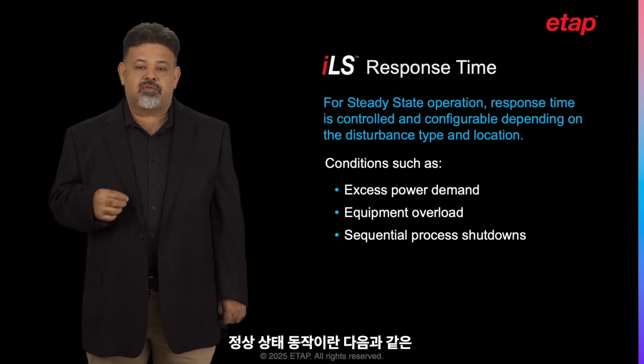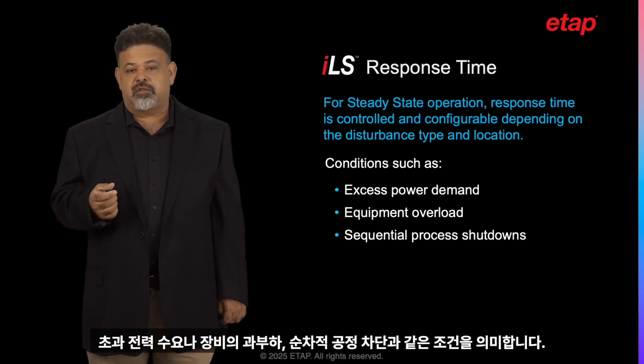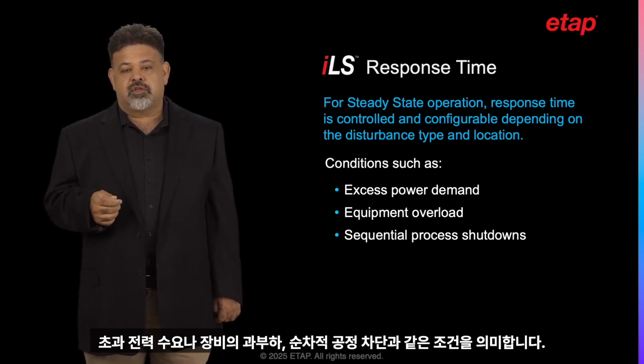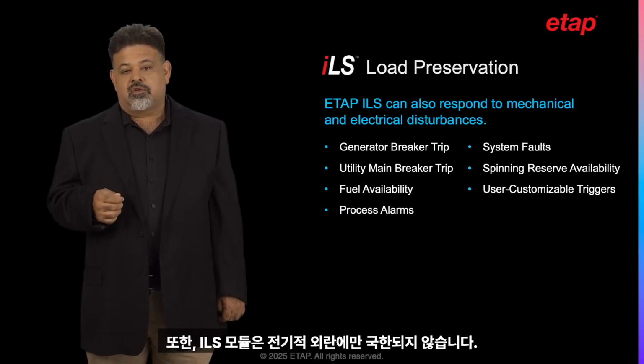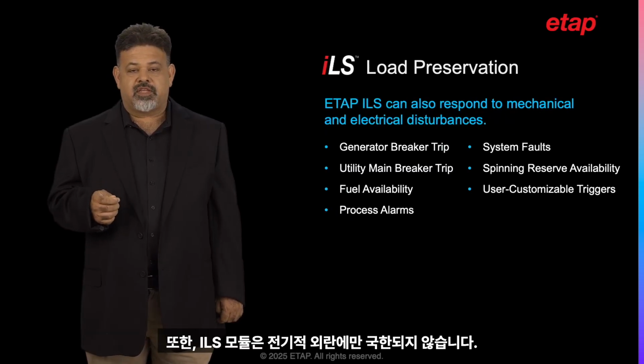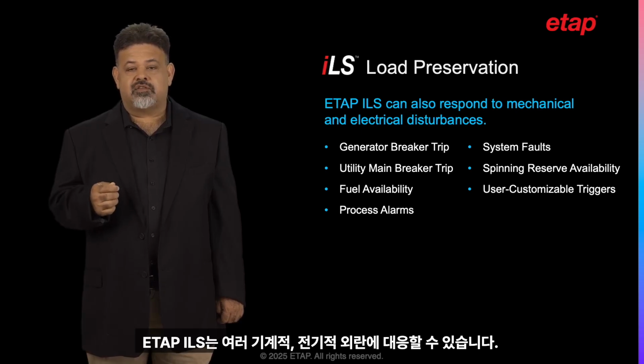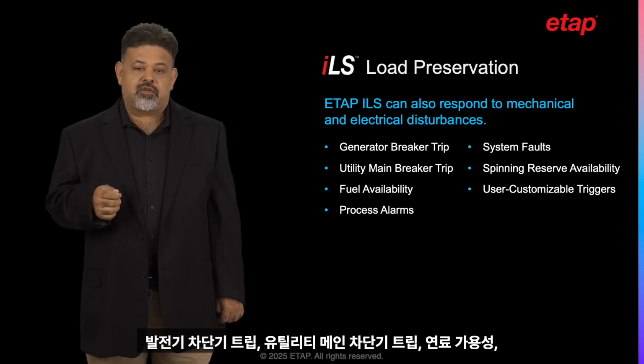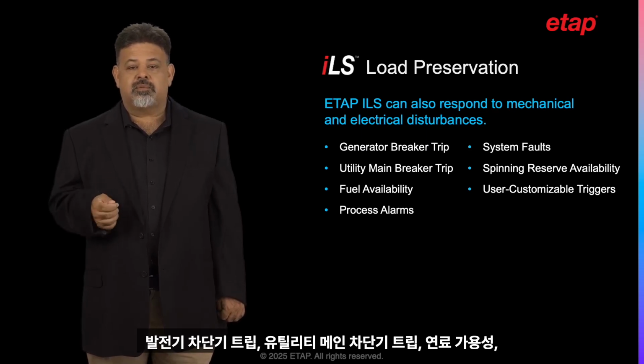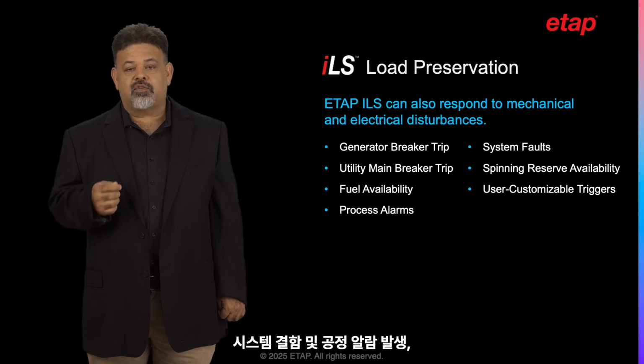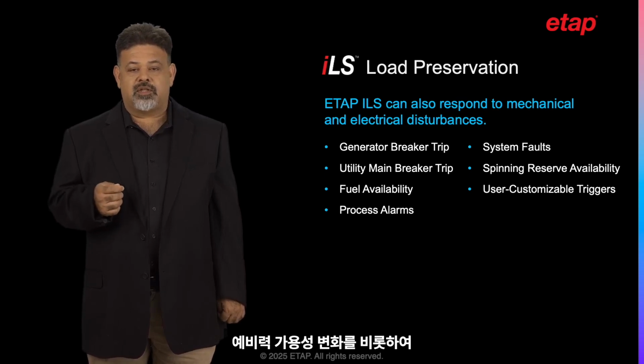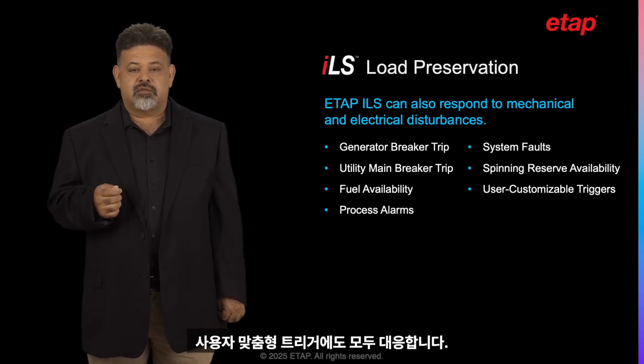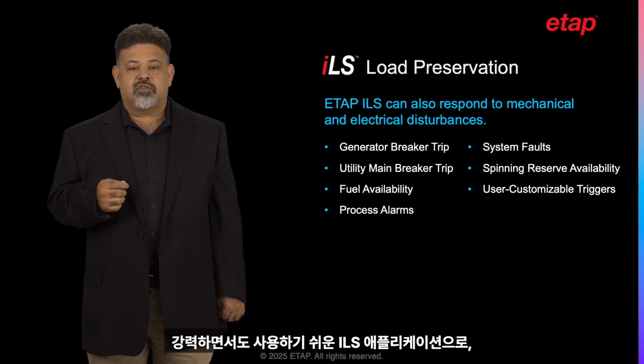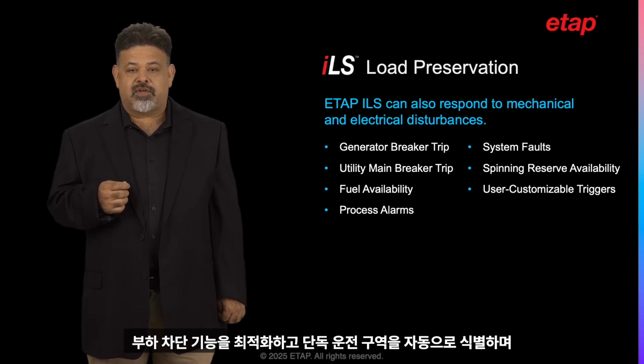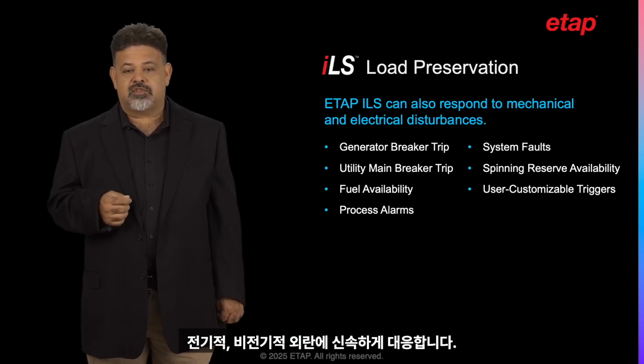Note that the steady-state operation refers to conditions such as excess power demand, equipment overload, sequential process shutdowns. Also note that ILS is not limited to electrical disturbances. ETAP ILS can respond to mechanical and electrical disturbances such as generator breaker trips, utility main breaker trips, fuel availability, process alarms, faults in the system, spinning reserve availability, user customizable triggers. In conclusion, the load preservation module is a very powerful yet easy-to-use application within ILS to optimize load sharing, identify islands, and respond to electrical and non-electrical disturbances.